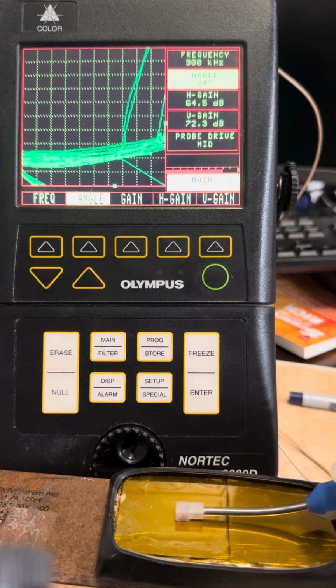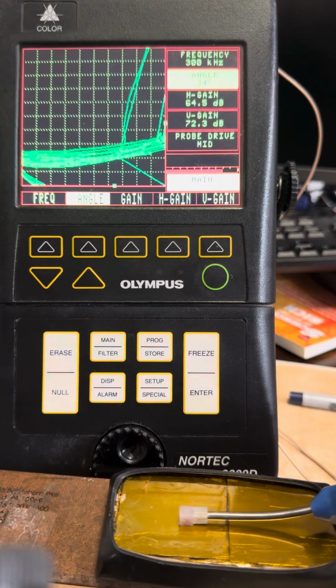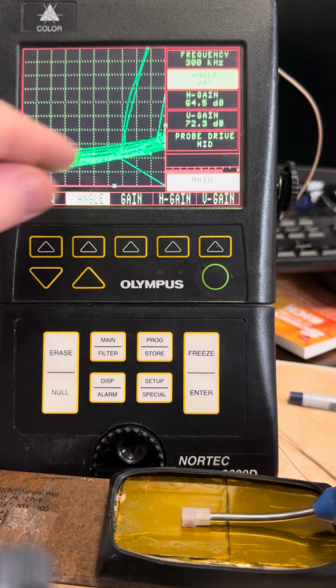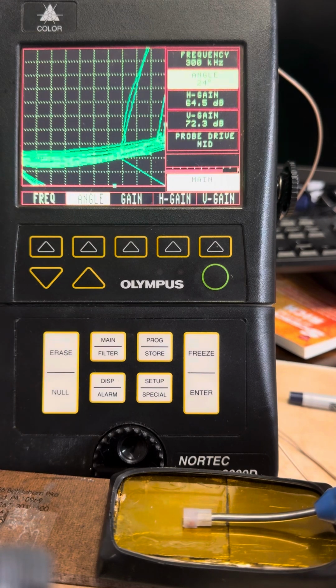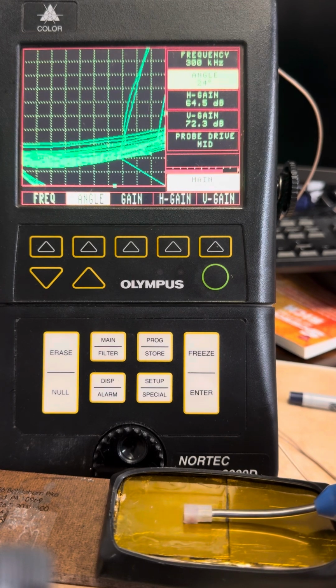But then when you go to the actual part you're going to test, if it's carbon steel, you might have to adjust the noise or the liftoff line a little bit. And you may want to position where your null point is. You can go up or down using the display. So it probably will take you a little bit to figure out where all these buttons are. But that's where your manual will come in handy. I think I emailed that to you already. So take a look at this.